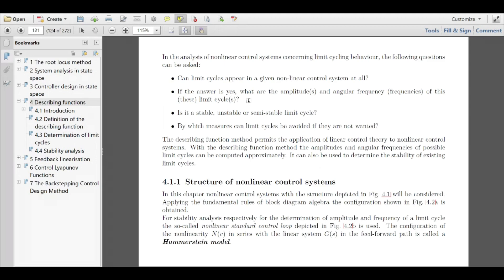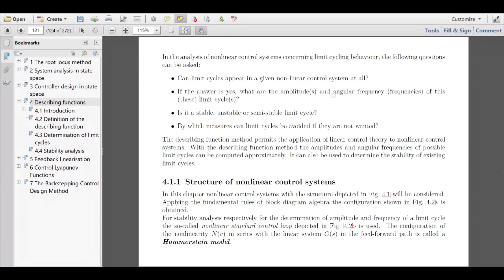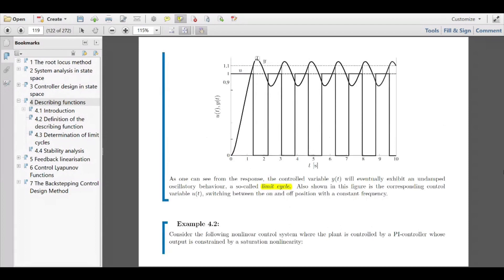Think of your room heating system: as long as the frequency is not too high, the control valve won't wear out too fast. You don't want it switching every second. Maybe it should switch every two to three minutes or every ten minutes. But why not every two hours? Because if switching only every two hours, the control error would get too large. So amplitude is somehow also associated with frequency, and you're interested in both.